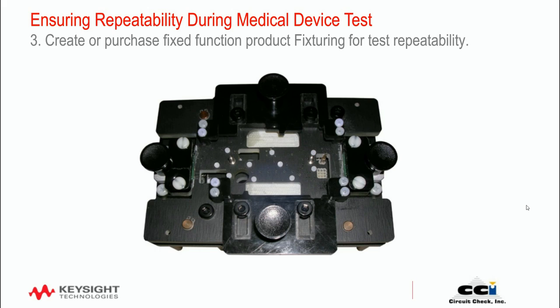In this example, the RF cables for conducted testing were attached directly to the top side of the PCB. The key point is that the knobs on the left and right allow one to replace the probe plates for different variants, while the top and bottom sliders hold the DUT down and ensure repeatability. It's a very simple setup, easy to reproduce, and easy to document within your R&D and validation plans.